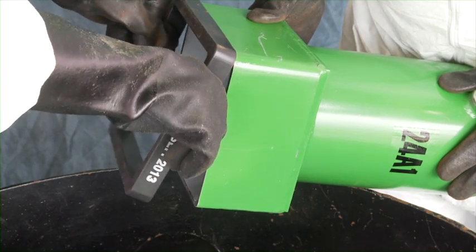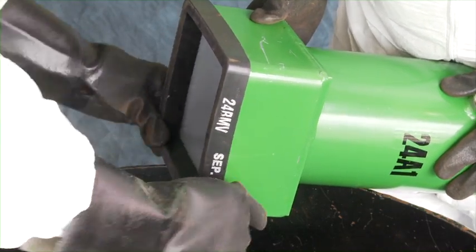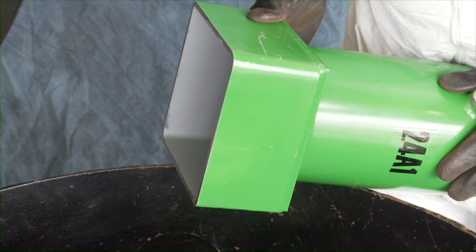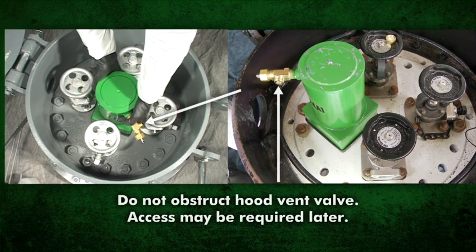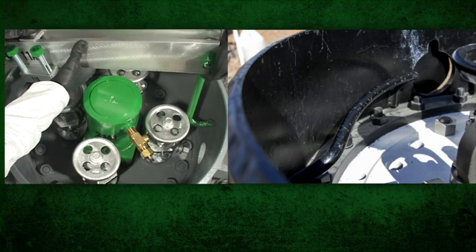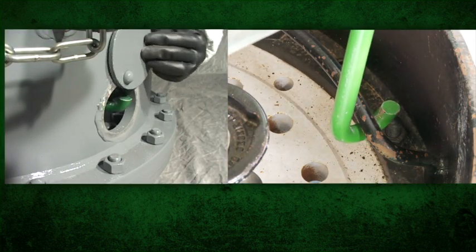Place gasket 24RMV on Hood 24A1. When ambient temperatures are low, it is desirable to perform this task in advance, preferably in a heated area. Also, the bottom edge of the hood should be smooth — nicks, cuts, or an uneven edge can prevent the hood from sealing against the pressure plate. Place Hood 24A1 with gasket 24RMV over the leaking pressure relief device. Do not obstruct the hood vent valve outlet as access may be required later. Place the yoke assembly 11A hooks into the port openings of the protective housing, or mounting bars in the protective housing if so equipped.